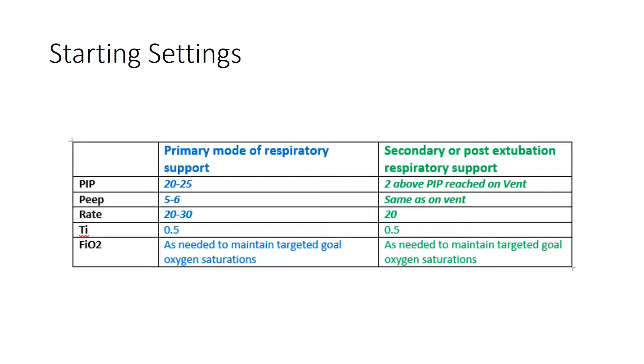When you're extubating to NIPPV, your starting settings will be slightly different. Your PIP will be 2 above your PIP reached on your ventilator. Your PEEP will be the same as it was on the ventilator. Your suggested starting rate will be 20, and again your I time will be 0.5. Your FiO2 will be adjusted to maintain oxygen saturation targets.